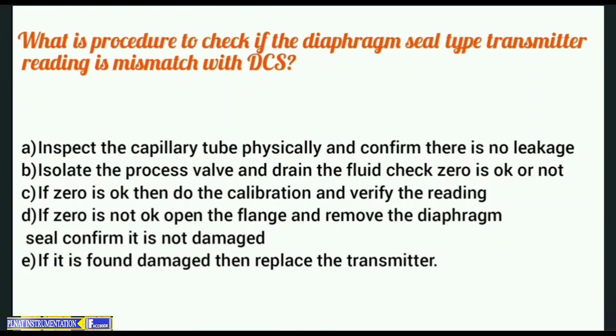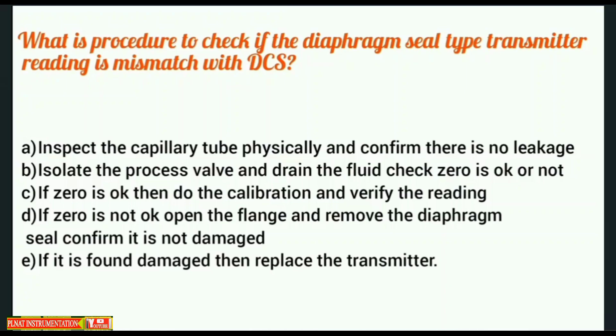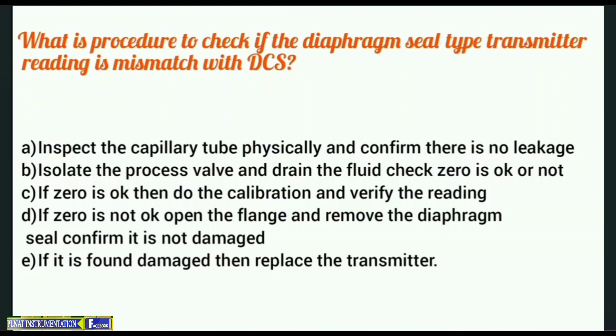What is the procedure to check if a diaphragm seal type transmitter reading is mismatched with DCS? A. Inspect the capillary tube physically and confirm there is no leakage. B. Isolate the process valve and drain the fluid. Check if zero is okay. C. If zero is okay, do the calibration and verify the reading. D. If zero is not okay, open the flange and remove the diaphragm seal, and confirm it is not damaged. E. If it is found damaged, replace the transmitter.